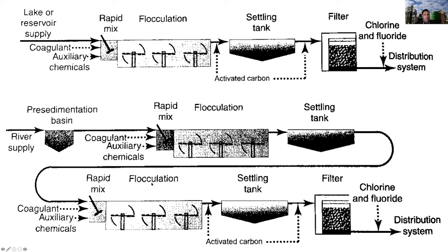Typical water treatment facilities treating surface water consist of the following processes: rapid mix after the addition of coagulant and some auxiliary chemicals, followed by flocculation which involves slower mixing. After the formation of flocs, we have settling and/or filtration to remove those flocs. Finally, we would have chlorination and fluoridation before the water is sent to storage and into the distribution system.